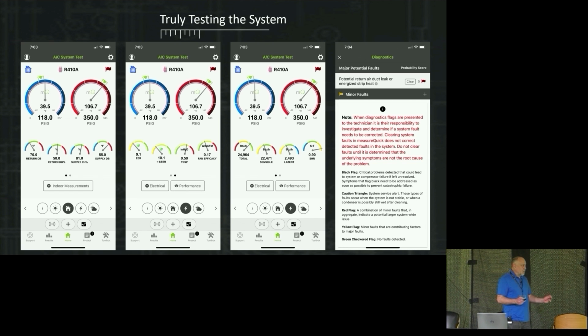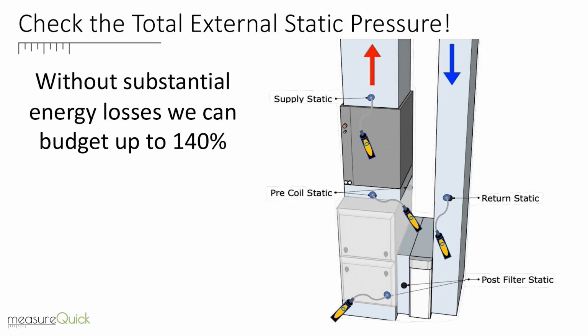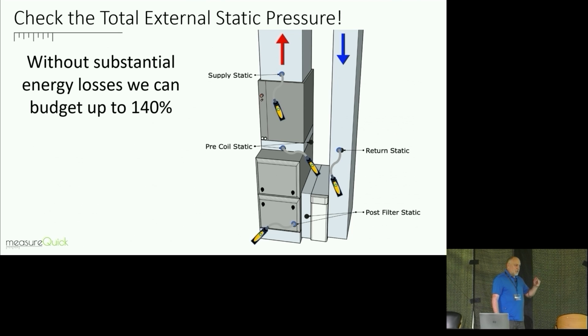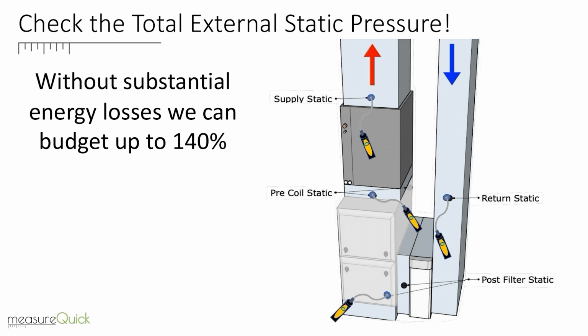If we're testing at the wrong spot, we're going to miss this problem, okay? So that's one of the most important things: truly test the system with MeasureQuick. Total external static pressure, we built static pressure testing into MeasureQuick now, and it will show you if your system has excessive static pressure. But this is a tricky one because a lot of people are measuring in the wrong locations. You'll see that your system's rated at a 1/2 inch of total external static pressure.